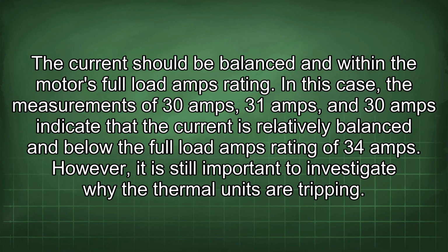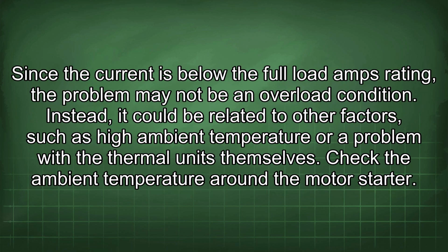In this case, the measurements of 30 amps, 31 amps, and 30 amps indicate that the current is relatively balanced and below the full load amps rating of 34 amps. However, it is still important to investigate why the thermal units are tripping. Since the current is below the full load amps rating, the problem may not be an overload condition. Instead, it could be related to other factors such as high ambient temperature or a problem with the thermal units themselves. Check the ambient temperature around the motor starter.